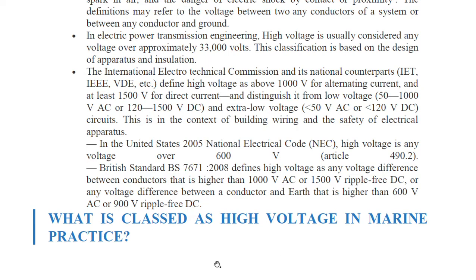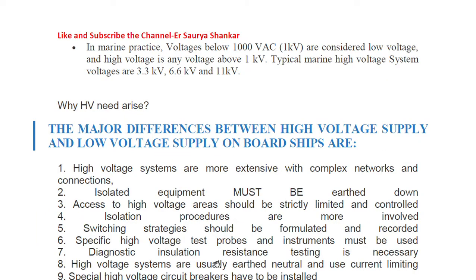In marine practice, voltages below 1000 V AC — that is 1 kV — are considered low voltage, and high voltage is any voltage above 1 kV. Typical marine high voltage system voltages are 3.3 kV, 6.6 kV, and 11 kV.